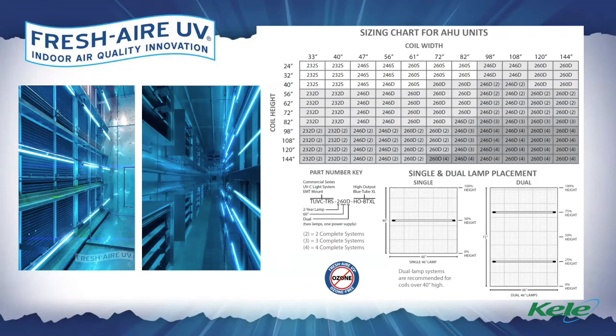But when we start shifting gears and using these coil mount units for air disinfection, we will suggest one lamp every 10 inches or so. That will make up for the fact that you have a much larger area to disinfect. What is nice about disinfecting in the air handling unit itself versus ductwork is that the velocity is slower. If we're seeing 1,000 feet per minute in the supply duct, then our system has to be designed in an orientation to maximize exposure at 1,000 feet per minute. In an air handling unit, it's going to range 400, 500 feet per minute. So the slower air velocity lends itself very well to ultraviolet.